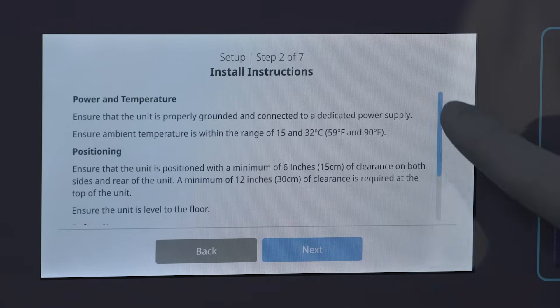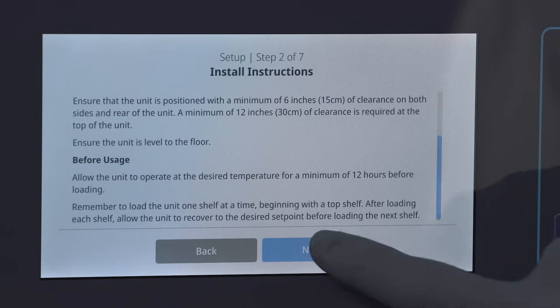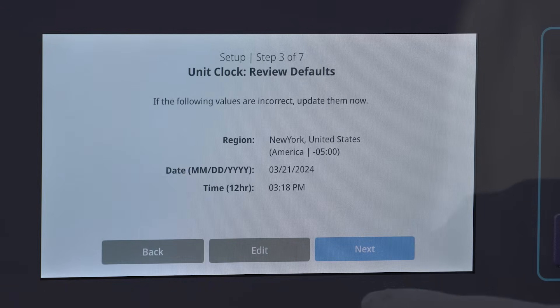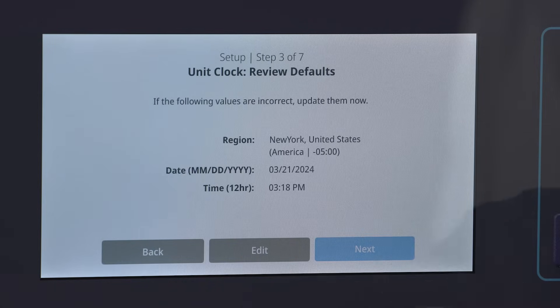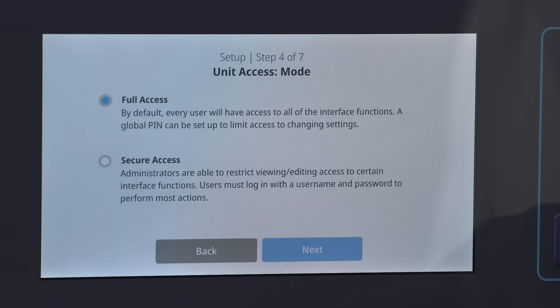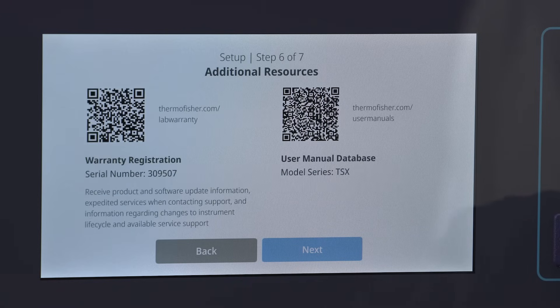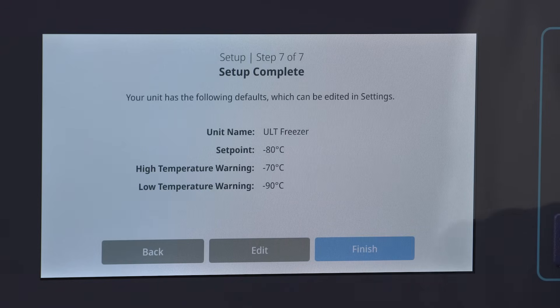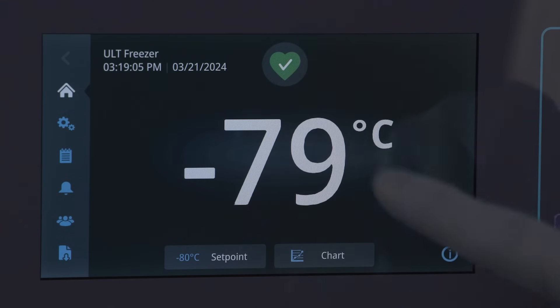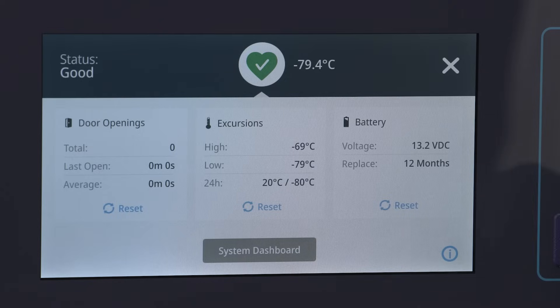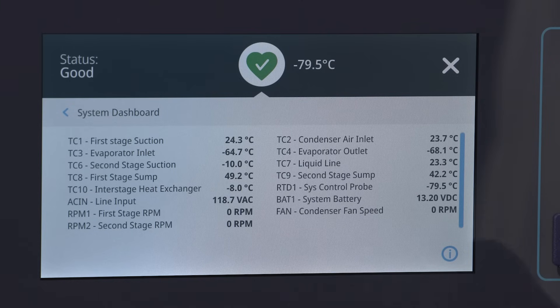The TSX Universal ULT Freezer is truly a universal voltage device. The internal electrical system is capable of any voltage within the operating range and provides the proper voltage to the refrigeration system components. No voltage step-up or step-down transformers are used, which means you get consistent performance and energy consumption regardless of the incoming voltage.